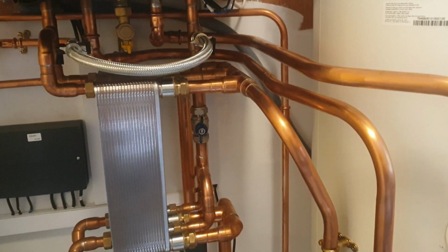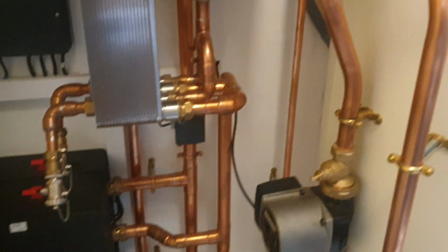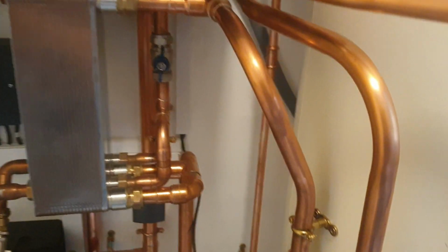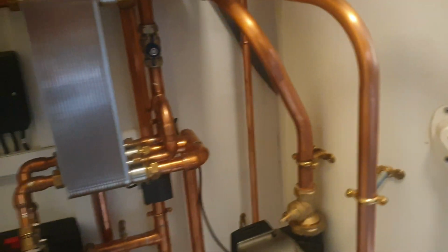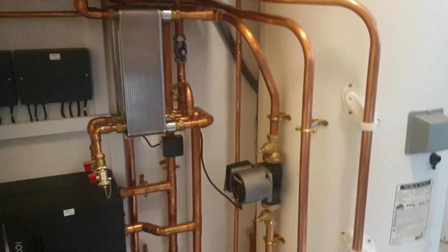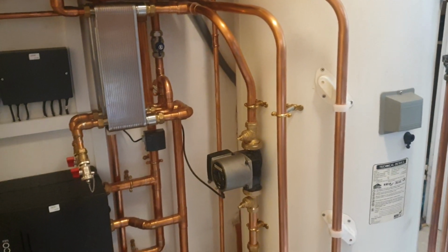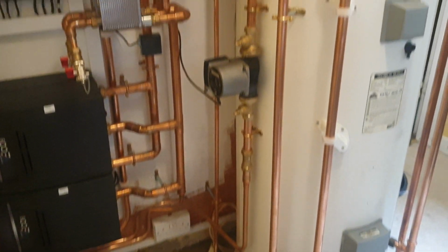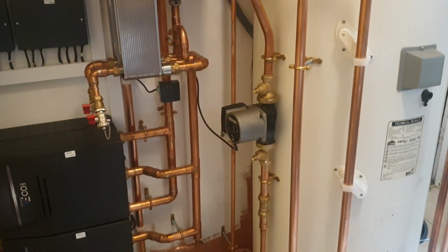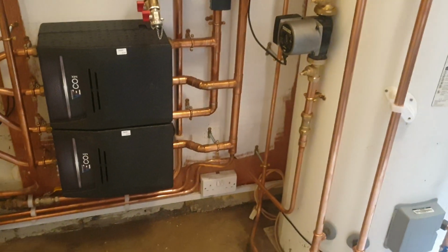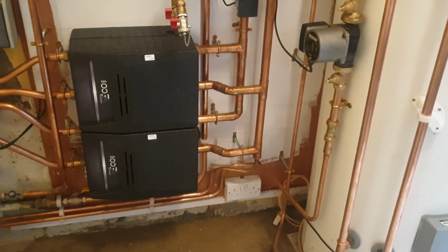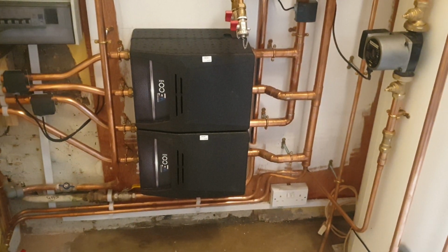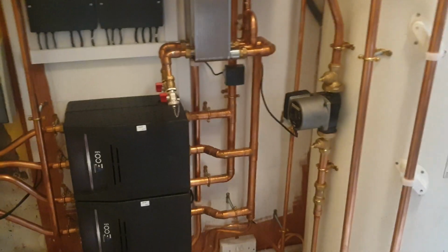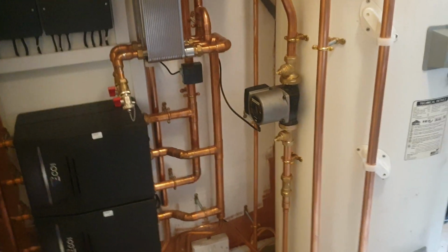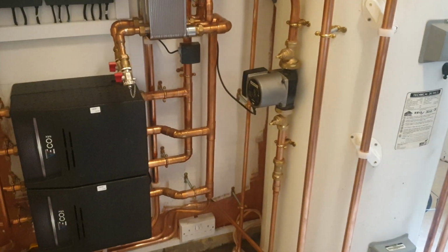A little bit of an interesting one here. There's my common flow sensor, and I've had to take off my flow to my unmixed circuit off the top here, so actually the boiler can't see the temperature of the common flow. So if they run that circuit on its very own, it could be a little bit confusing for the boiler. But that's very unlikely to happen. If the radiators are on for those 2 rooms, almost certainly the rest of the circuit is going to be on, so that common header sensor will show the common temperature, which will allow the boiler to know what the temperature is there.